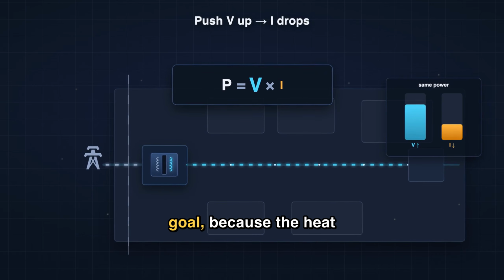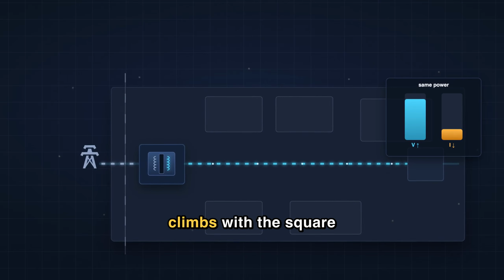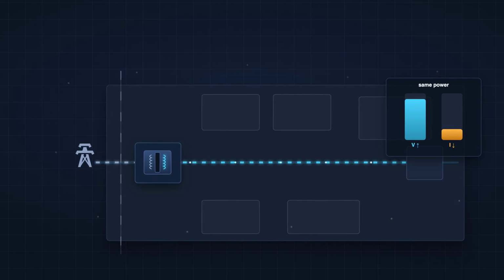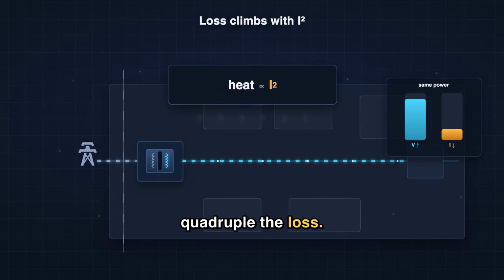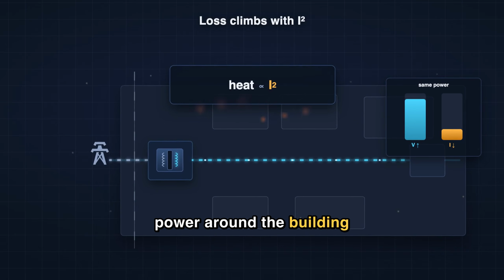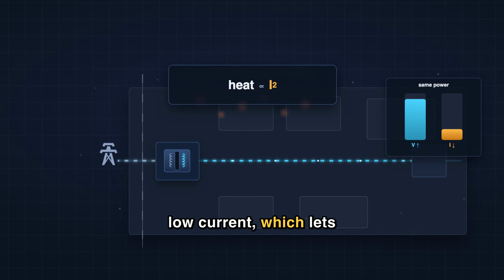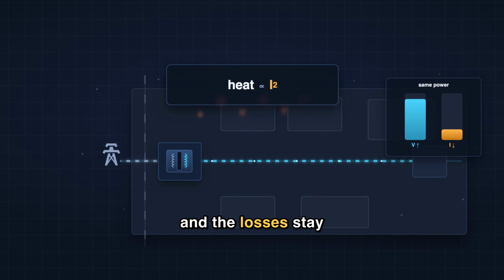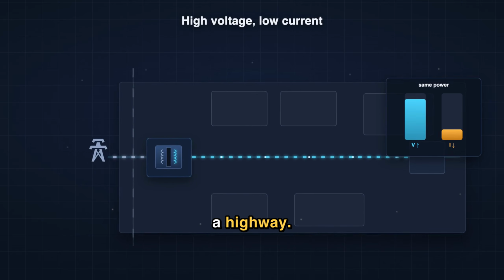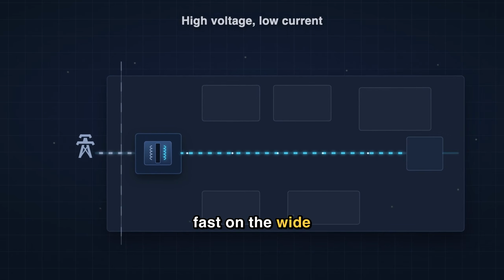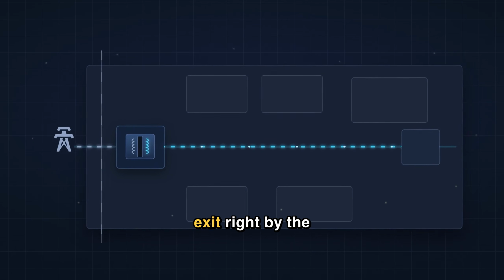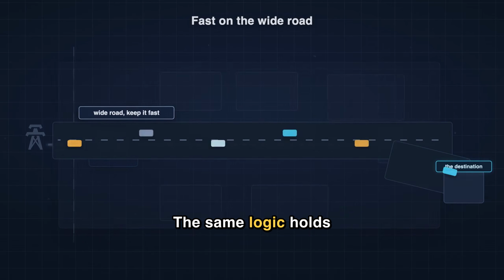Low current is the goal, because the heat wasted in a wire climbs with the square of the current running through it. Double the current, quadruple the loss. So the network moves power around the building at high voltage and low current, which lets the copper stay reasonable and the losses stay small. Think of it like a highway. You keep traffic moving fast on the wide road and only slow it down at the exit right by the destination. The same logic holds here.